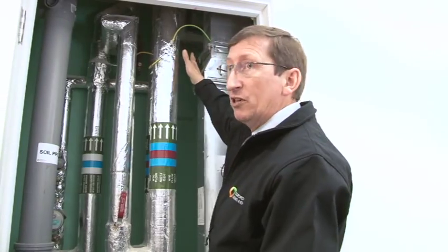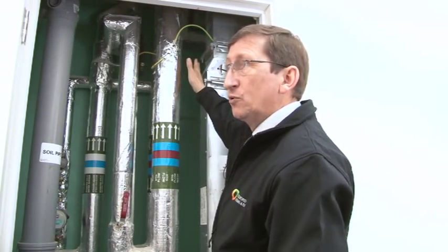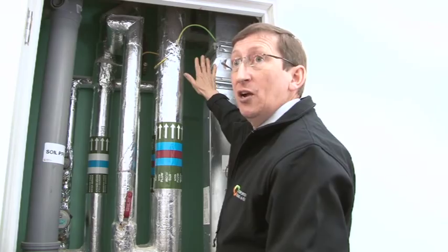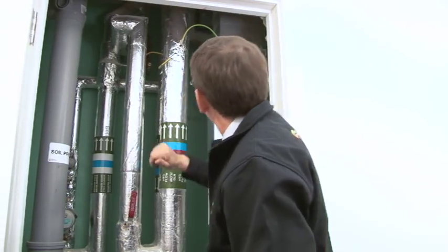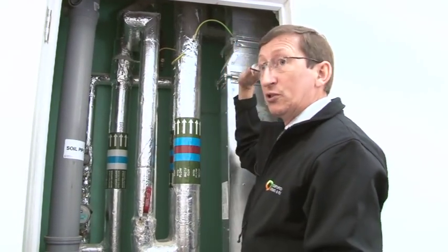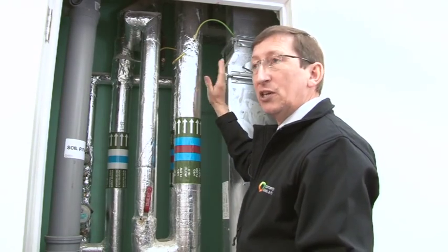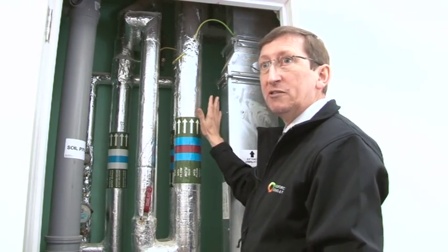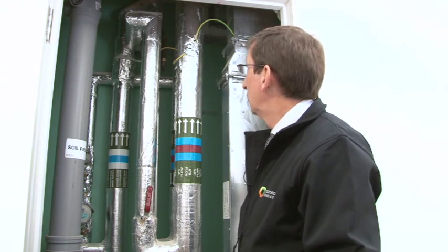There's a fire damper in there which is resettable. If there was a fire, that gives the isolation from the flat at that point. And there's also a control damper that sets the airflow into that flat, but that's all set at commissioning stage and then doesn't need altering any further after that.